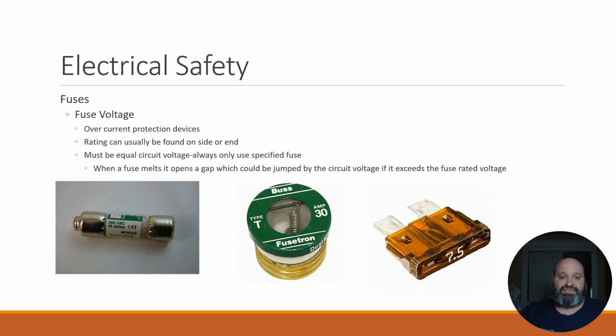Usually the rating is on the fuse itself. Again, if you use too small of a fuse and there's an overcurrent situation, hopefully that would just be temporary. But if there were, the fuse would melt, but then current can jump the gap and continue to energize the rest of the circuit. So definitely never a smaller fuse. And if you put a bigger fuse in, let it only be because you're going around the corner to get the right sized fuse and coming right back. But really, you shouldn't even do that. What you should do is leave the system de-energized and go get the right sized fuse and then come back. So just use the right fuse.